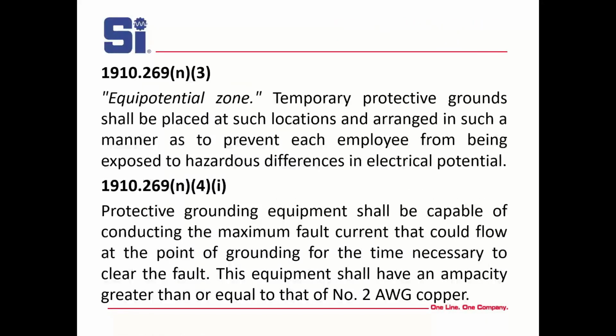Equipotential zones. I'll speak a little bit going in. I don't have time to take it up a lot, but they have to be arranged in such locations in such a way that you're provided an equipotential zone. And that means that as long as you're within the equipotential zone, you are safe. If you take your foot and you leave the equipotential zone, say goodbye to your family. You aren't going to be there anymore.